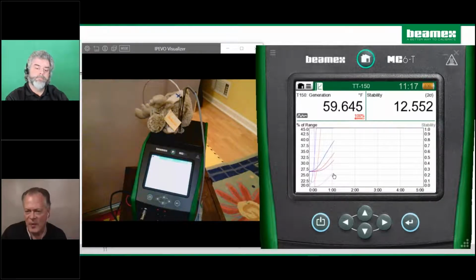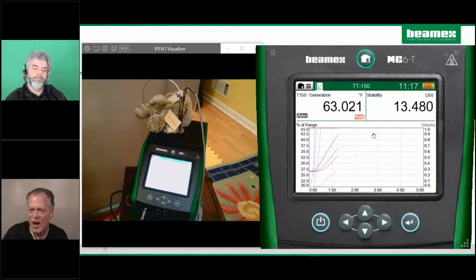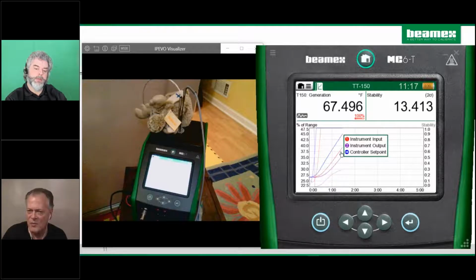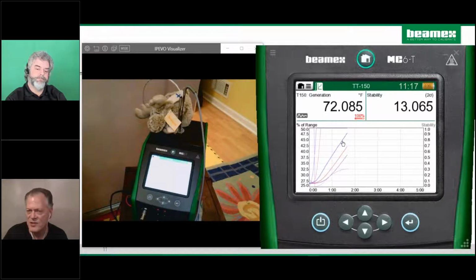So there's a bunch of lines on this graph, but we were basically at 28% of range, whatever 40 divided by 150 is. And now the temperature's taking off, trying to get to 100% of range. But it's plotting 3 things here. If I click, it's showing that the instrument input is my traceable reference probe. The controller set point is this blue line. And this is actually the controller temperature here. So the controller temperature is moving the fastest compared to the reference probe. And then the last element is the milliamps. So here's the milliamps, and it's kind of tracking in parallel with the reference probe.